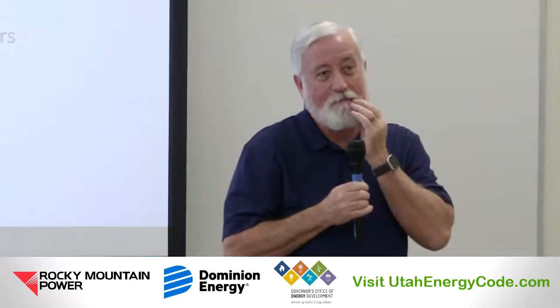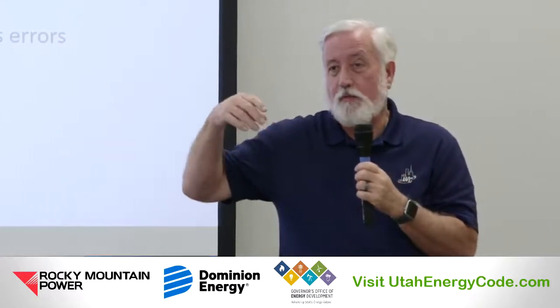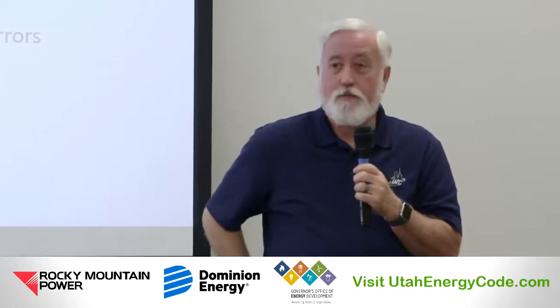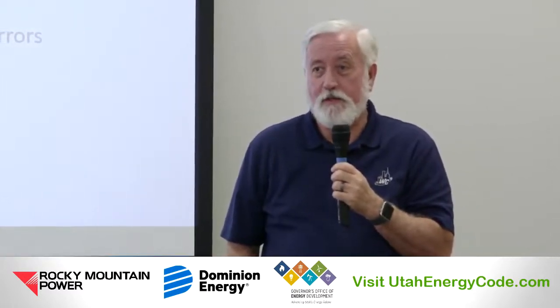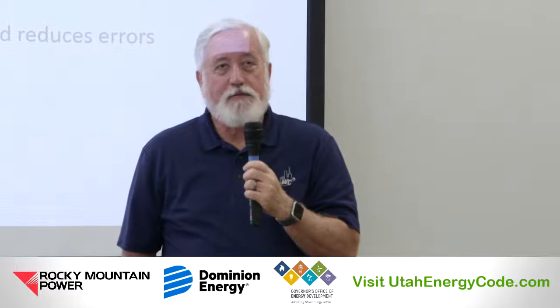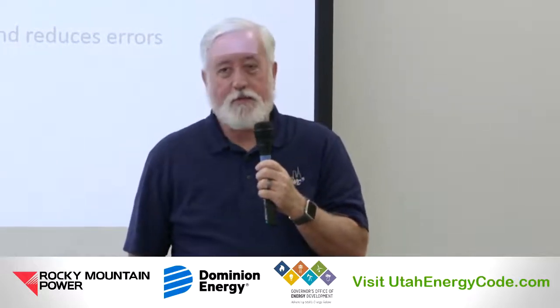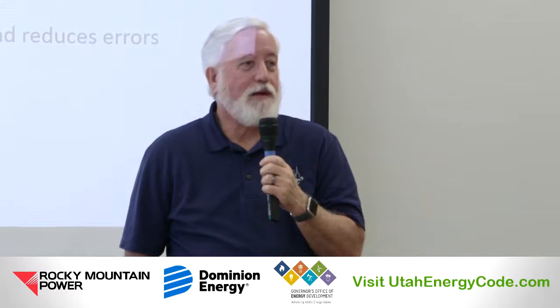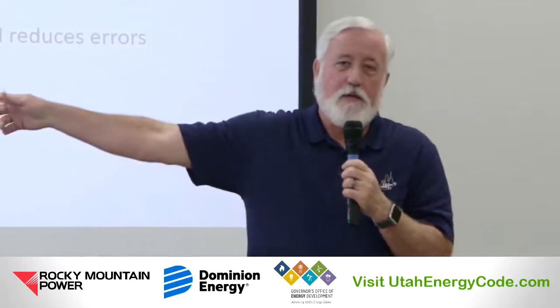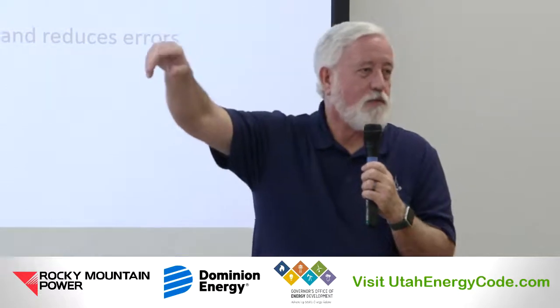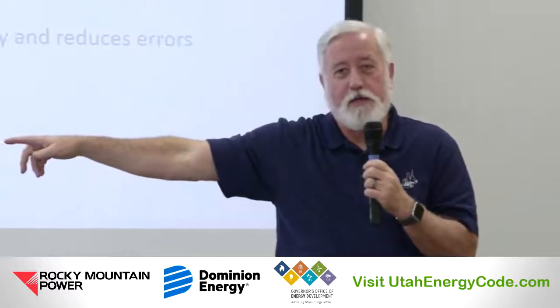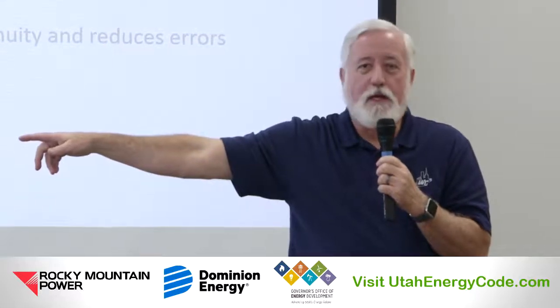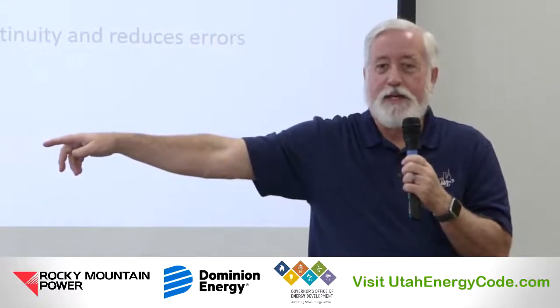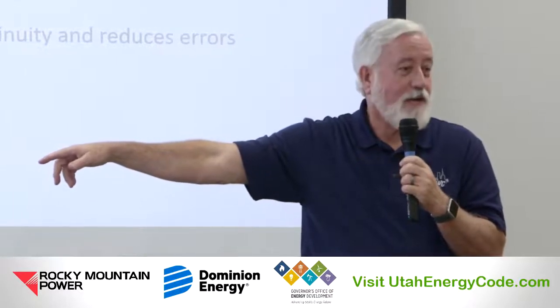Kind of confusing, isn't it? It really is. But for any single family dwelling, a standalone home, the blower door test is 3.5 air changes per hour at 50 pascals. Simply what we're doing is identifying leakage in the house by elevating the pressure. I can almost guarantee a half a dozen or a dozen of us in this room have a wheelbarrow out in the backyard that might not look like it has a flat tire, but if you put any weight on it, it has a flat tire, right? And it's going to go flat.